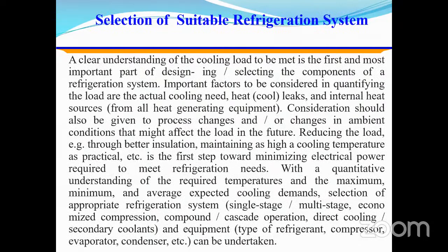Selection of a suitable refrigeration system. A clear understanding of the cooling load to be met is the first and most important part of the designing and selecting the components of a refrigeration system. Important factors to be considered in quantifying the load are the actual cooling need: heat leaks and internal heat sources from all heat generating equipment.